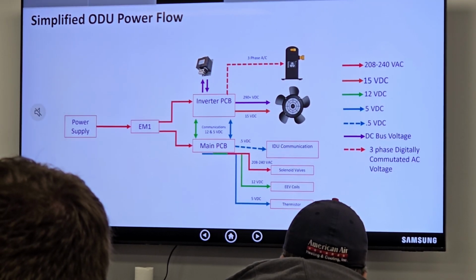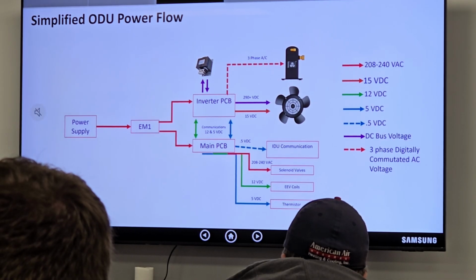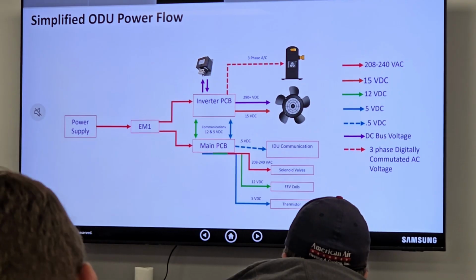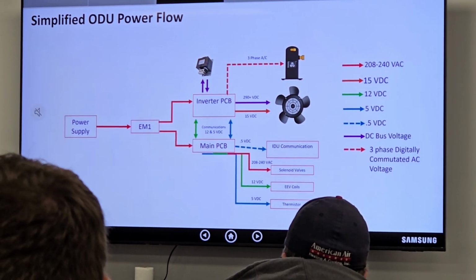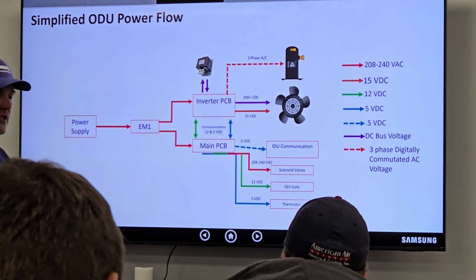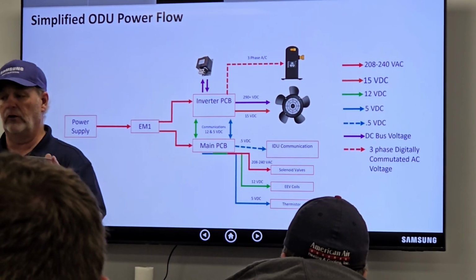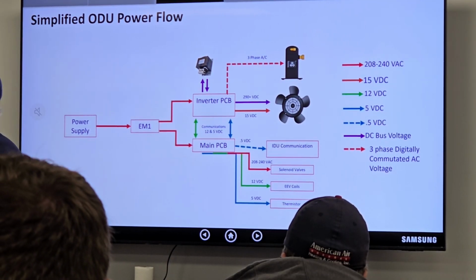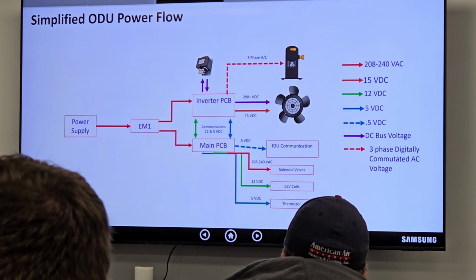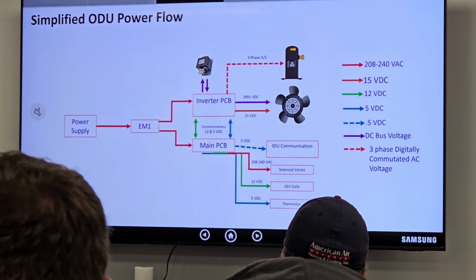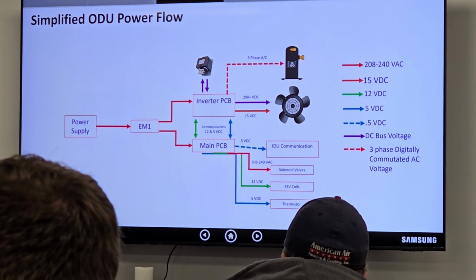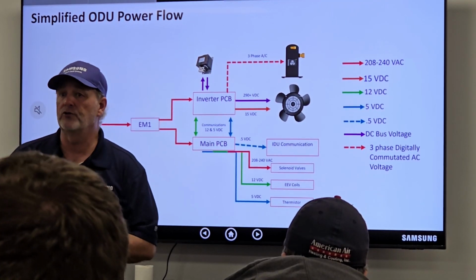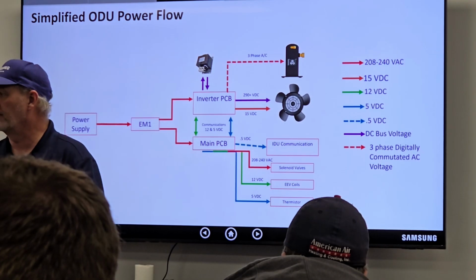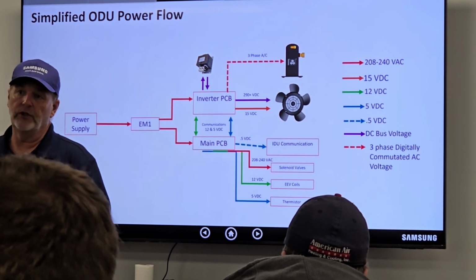Now at the same time, talk about communication wire. What's also different with this wire? It's shielded. Why would we want to shield the wire? So it won't mess with the signal. Correct. We are using a DC signal, so if this runs across a high voltage feed, what can we do? Slow everything. We can scramble it. If this wire goes in the same conduit as a high voltage wire, what can it do if it's not shielded? It can affect it. Electromagnetics can affect my communication because of the differential voltage. Doesn't take much to do that, does it? So ultimately we do use a shielded cable.